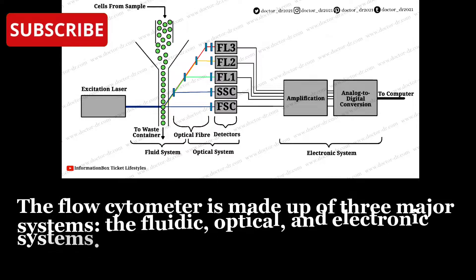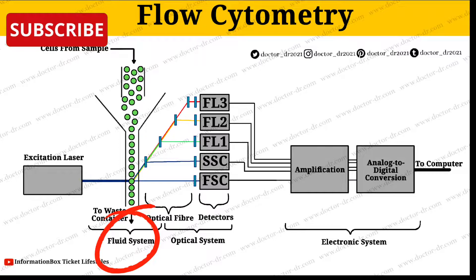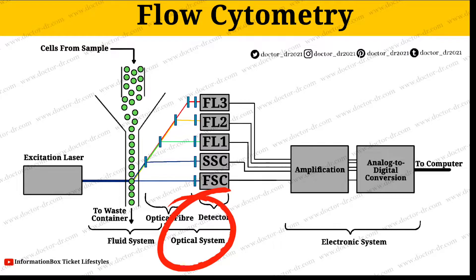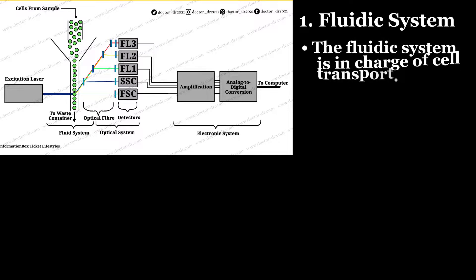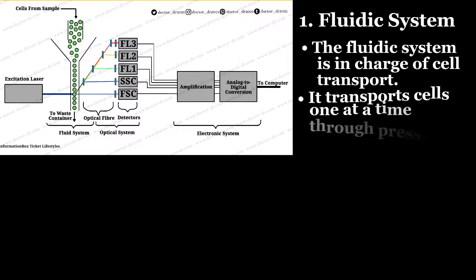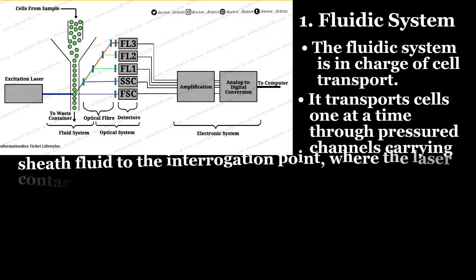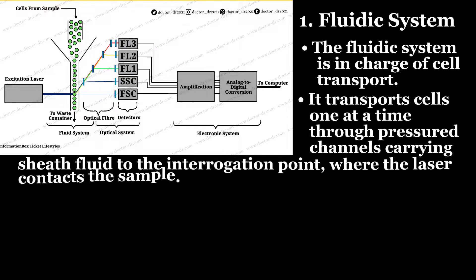With the help of the diagram, you can see that flow cytometry is made up of three major systems: number one, the fluidic system; number two, the optical system; and number three, the electronic system. The fluidic system is in charge of cell transport — it transports cells one at a time through pressured channels carrying sheath fluid to the interrogation point where the laser contacts the sample.